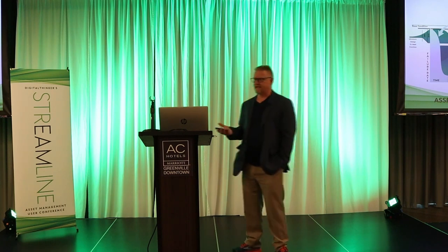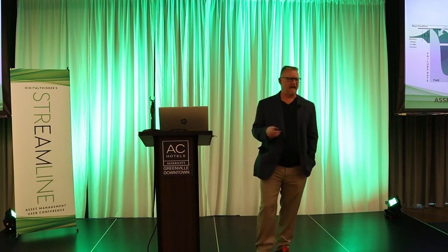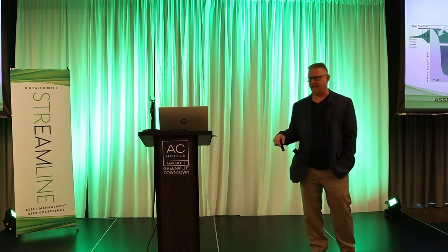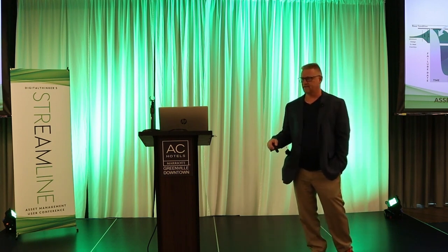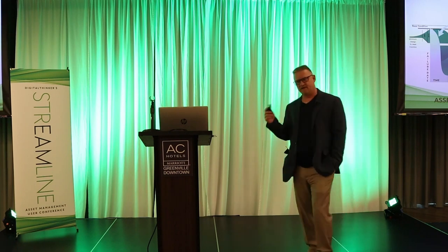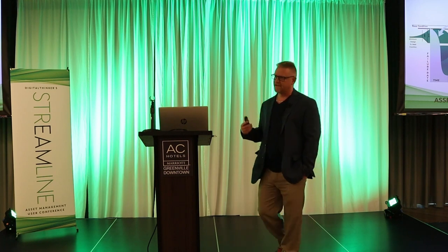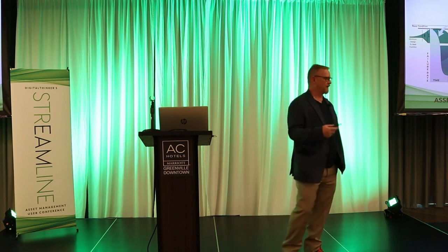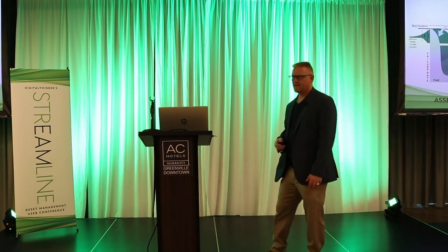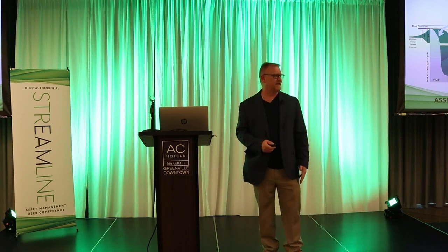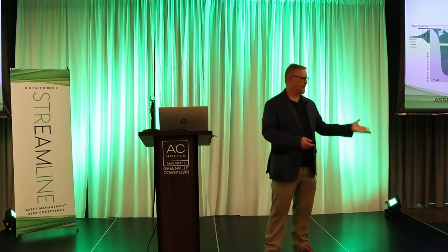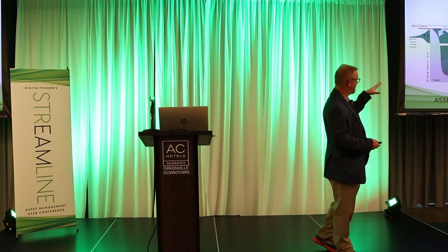So if we PM things too often and we do a bunch of extra work just because we're there, oftentimes we're doing damage to the asset. We're not helping the asset. Usually, the lowest frequency visit to an asset is due to its lubrication requirement. So most rotating assets that require lubrication, we go to at some frequency, whether it's monthly or quarterly, depending on the bearing in the asset. And then we have this long task list of stuff to do just because we're there. And it doesn't really need that. And so when we use the FMEA process, we change those things and we end up with a different baseline.